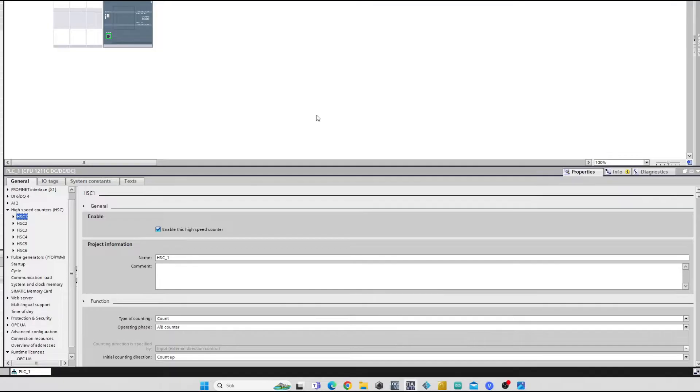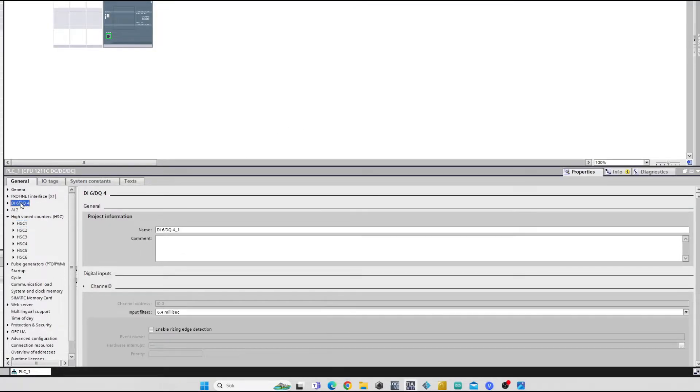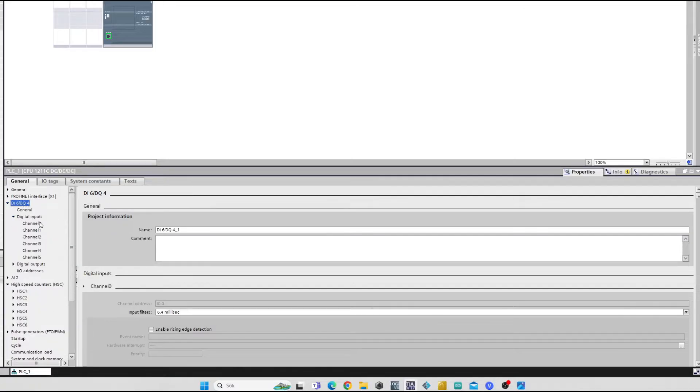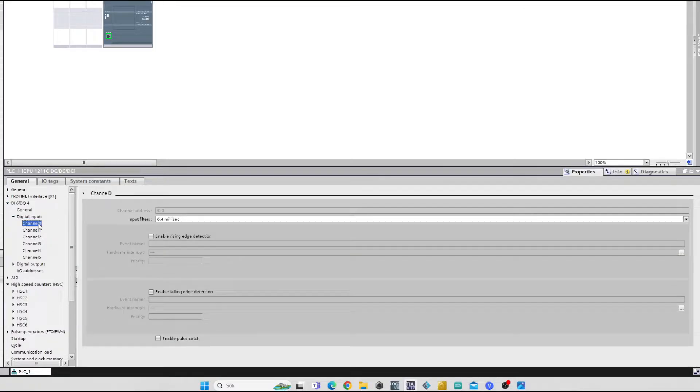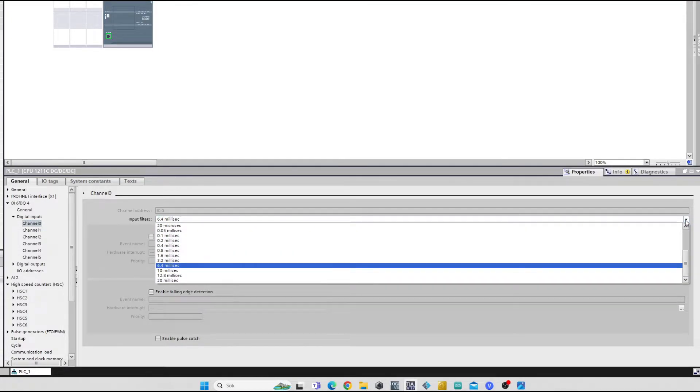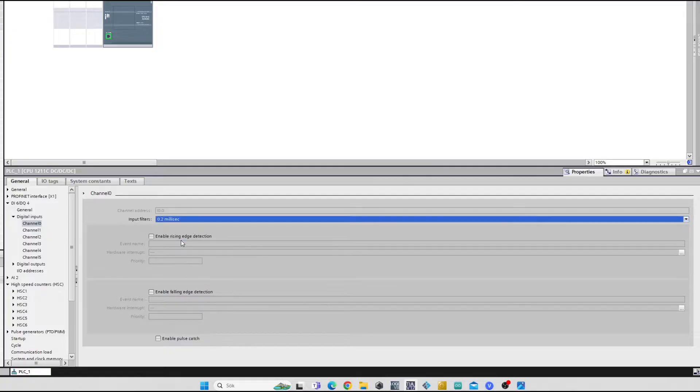Next we want to go to our PLC Digital Input Settings and change how fast our input 0 and 1 can read our signals from the encoder. We want to change it from the standard 6.4 milliseconds to 0.2 milliseconds on both channels.